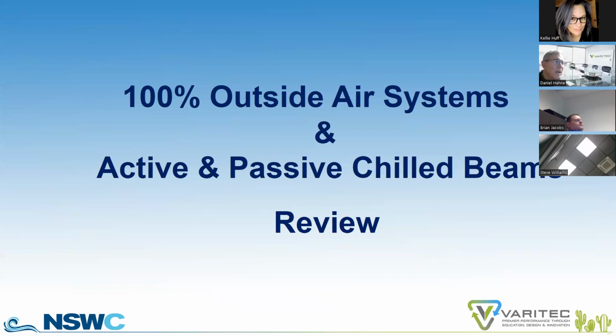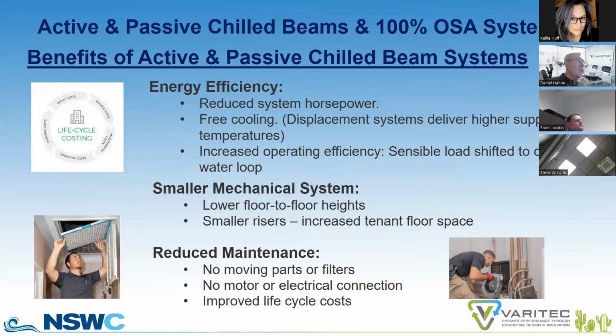So 100% outside air systems, active and passive chill beams. Just a quick review. Active and passive chill beam systems are more energy efficient because they reduce system horsepower. You have opportunities to maximize free cooling, certainly with a passive system and doubling your economizer hours. You increase operating efficiency. These systems, because of the significantly reduced ductwork, lend themselves to lower floor heights, smaller mechanical room footprints. So there's some real estate advantages architecturally to be aware of.